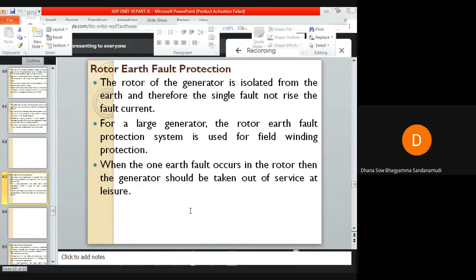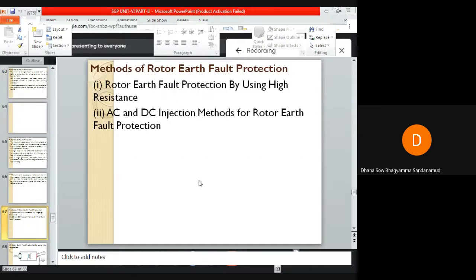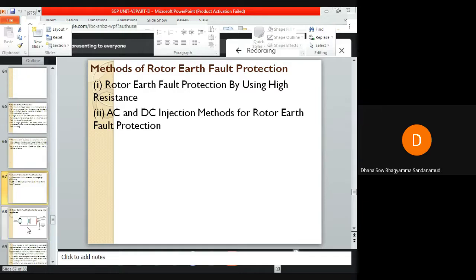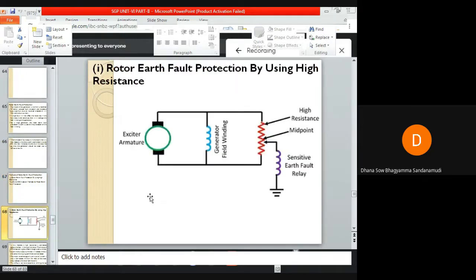So there are two methods of rotor earth fault protection. One method is by using high resistance, and another method is by AC/DC injection. So one method of rotor earth fault protection is by using high resistance. Another is the AC/DC injection method for rotor earth fault protection. Let us discuss these two protections one by one. First is rotor earth fault protection by using high resistance.